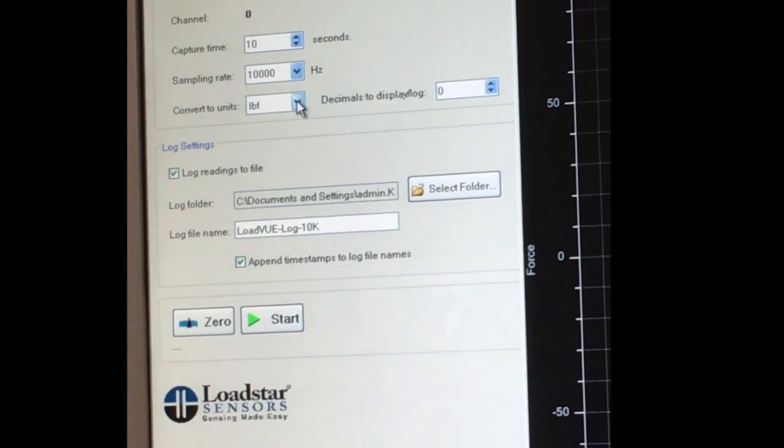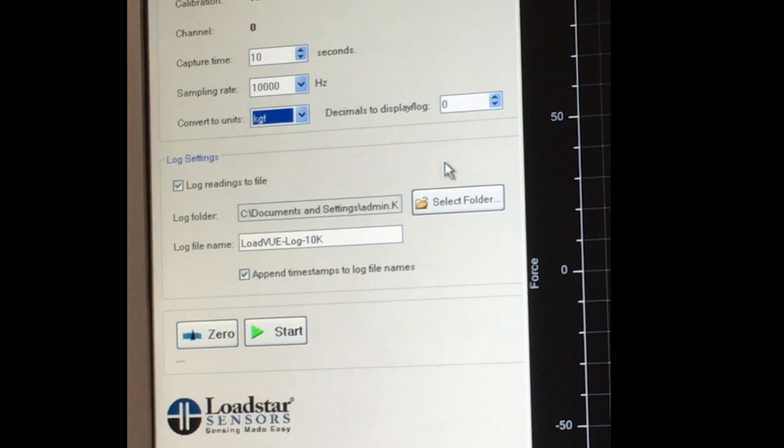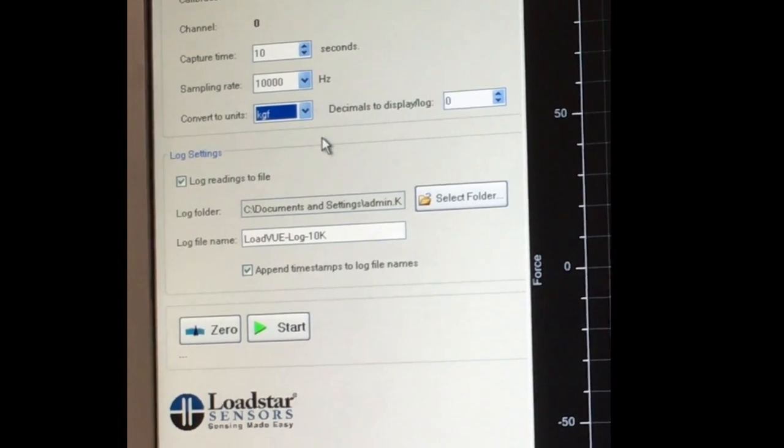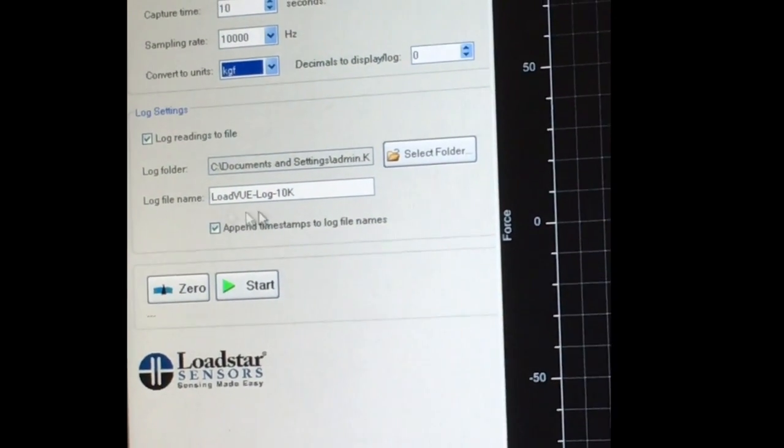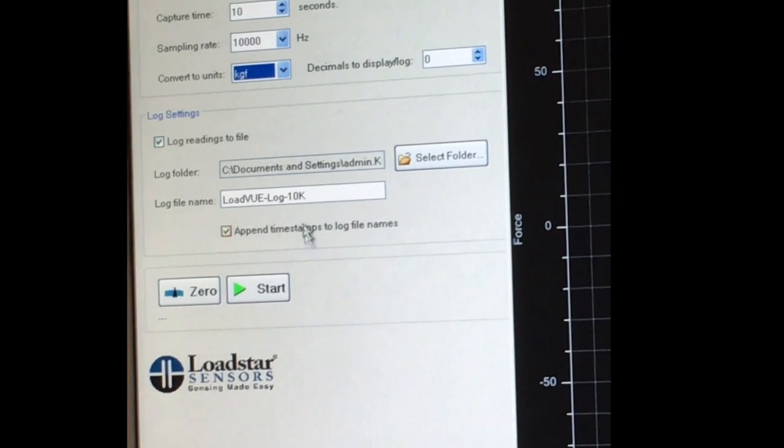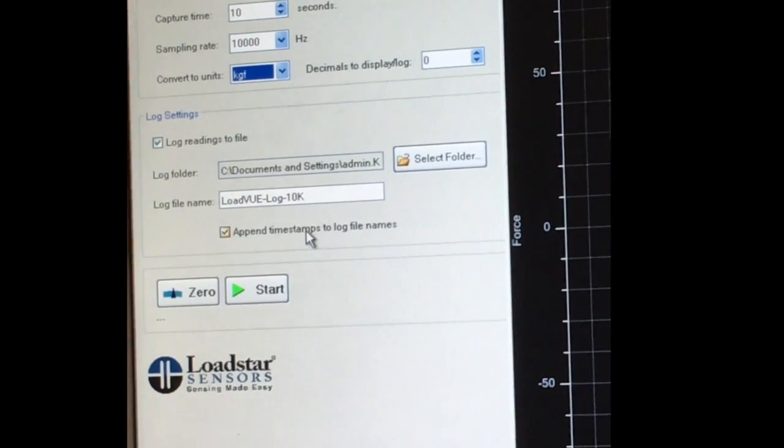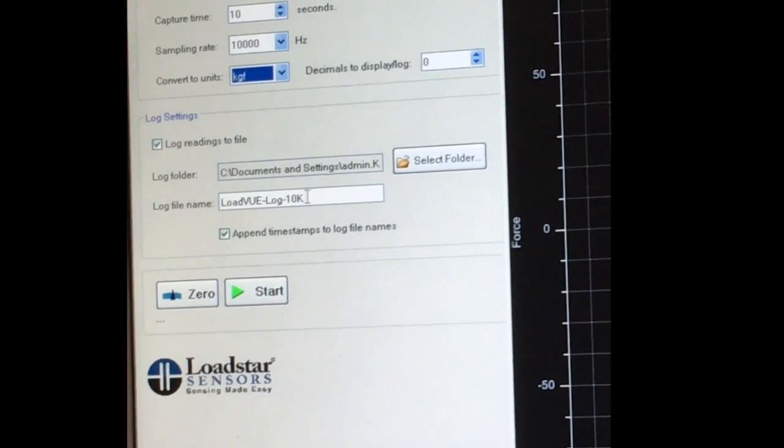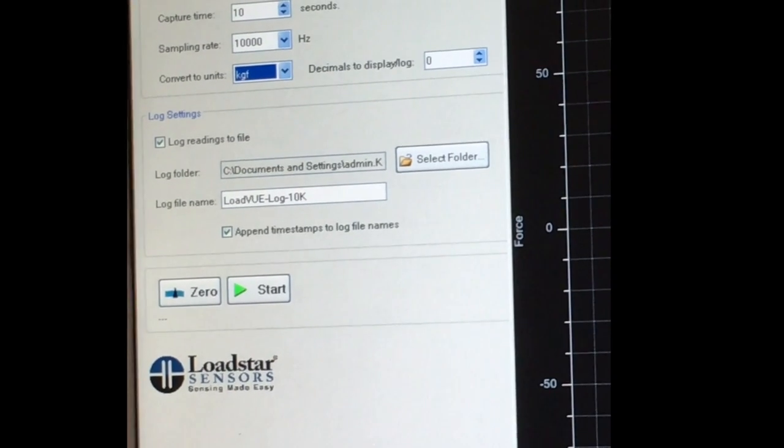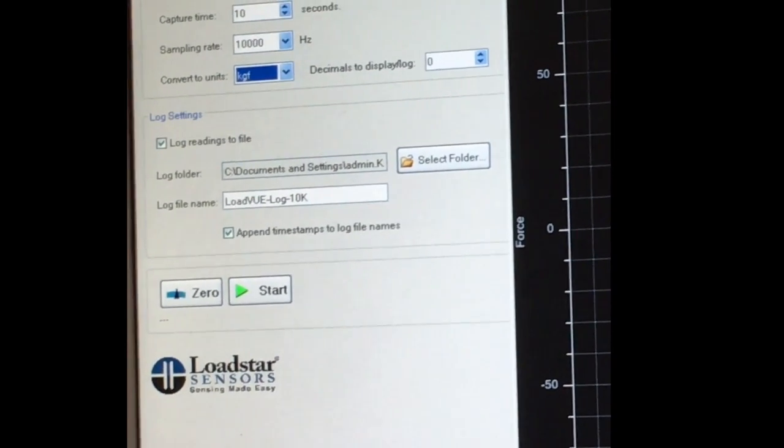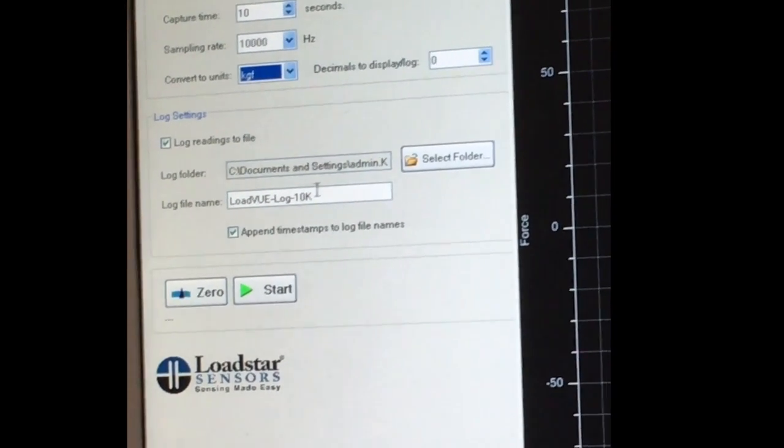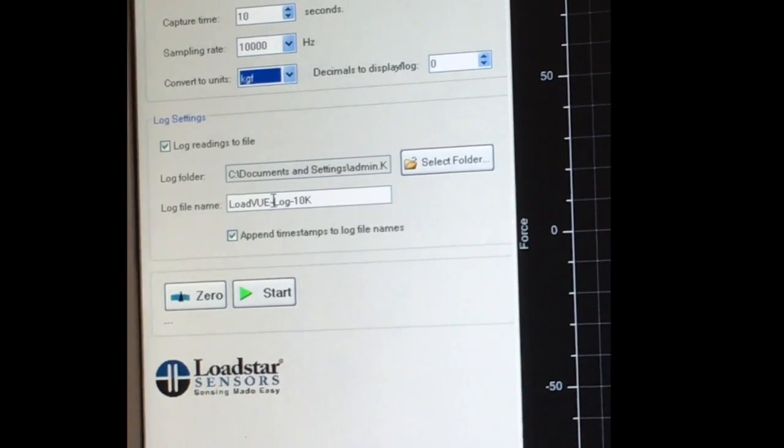We can do it in pounds or kilogram, so let's say in kilogram. This shows you the file name under which you can log the data if you wish. Since you'll see the data, but you probably want to log the data and then open it in Excel, just enter a file name. Before you use it, just say zero it, zero load.